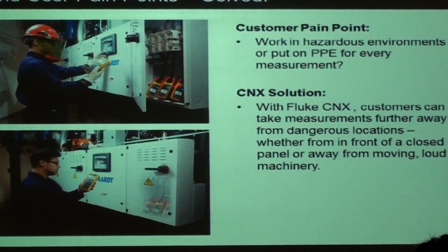In applications like long-term logging, whenever you remove enclosures you have to wear PPE, which can be a cumbersome process. So you can leave these clamps inside, and even without PPE, I can just walk up to the panel and see the actual reading. This avoids having to wear all that PPE every time. You can leave the meters in there as long as the battery lasts, and these batteries will run for around 400 hours. If you switch on the radio, battery life is reduced, but it switches off after a certain time, so there's a sleep mode to save battery.